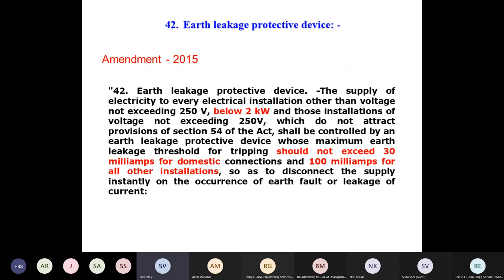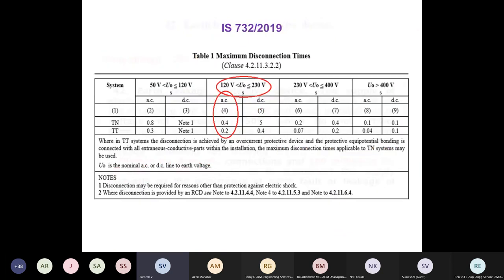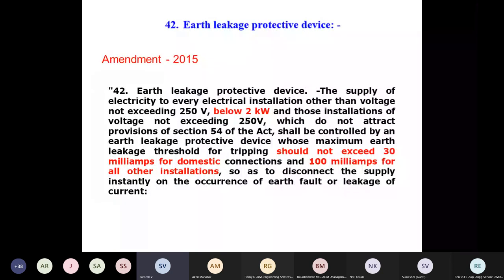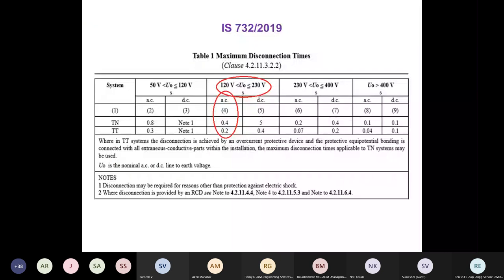As per Regulation 42 of the Central Electricity Authority measures relating to safety and electric supply, all installations with a connected load greater than 2 kilowatt should provide an earth leakage protection device at the origin. In Kerala, the Kerala government insisted on RCCB for all consumers for getting an electric connection. This is the IS 732 requirement about the RCCB. In a TN system, the operating time may be up to 0.4 second. In a TT system, it should be less than 0.2 second, that is 200 milliseconds.